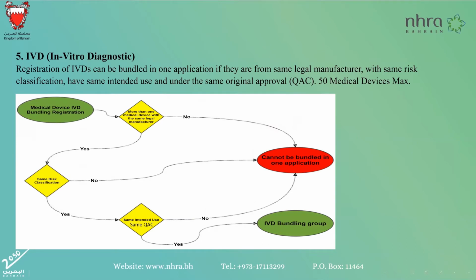And the final bundling group is the IVD, or in vitro diagnostic bundling group. As the name suggests, it is for IVDs only. So if the IVDs to be bundled are from the same legal manufacturer, have the same risk classification, same intended use, and are under the same quality assurance certificate, then they can be bundled together in one application. For this bundling group, also 50 devices is the maximum for each application.